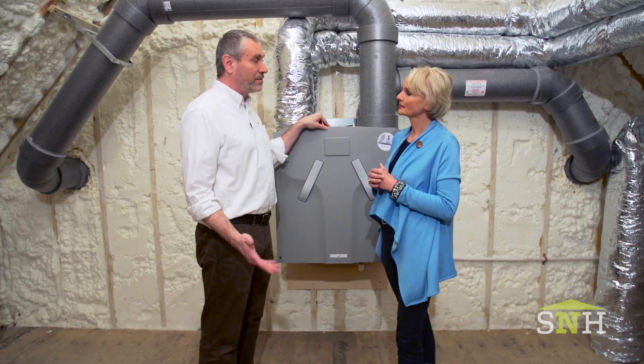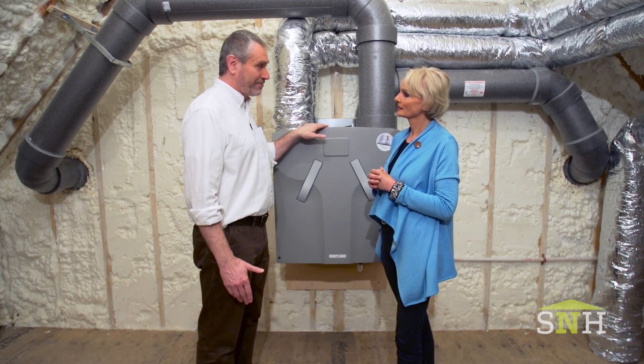It's always a heat transfer process, and it always works — it's the simple marvel of physics. So that is all about energy efficiency too. Up to 90% of the temperature difference can be recovered, and about two-thirds of the humidity, which is great in a climate like Greenwich. Being near the ocean and somewhat warm in the summertime, you can lower your air conditioning needs and dehumidification requirements by having an ERV.